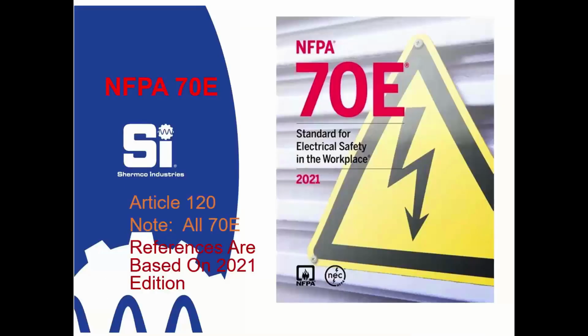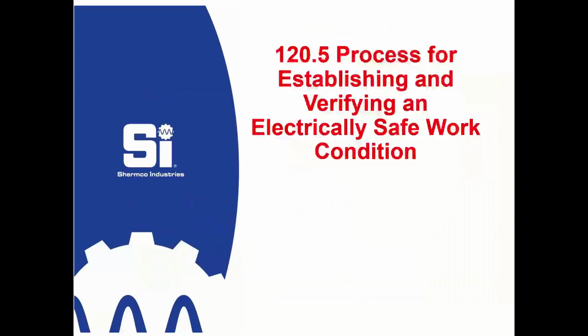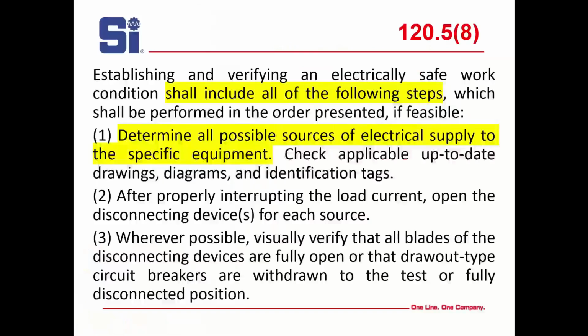Then we'll talk about NFPA 70E. I go off the new edition, and you'll find most of the information concerning personal protective grounding is in Article 120. It's in Section 120.5. Now, I've highlighted some important points that I want you to be aware of. Establishing and verifying an electrically safe condition shall include the following steps. 1, determine all possible sources of electrical supply to the equipment.